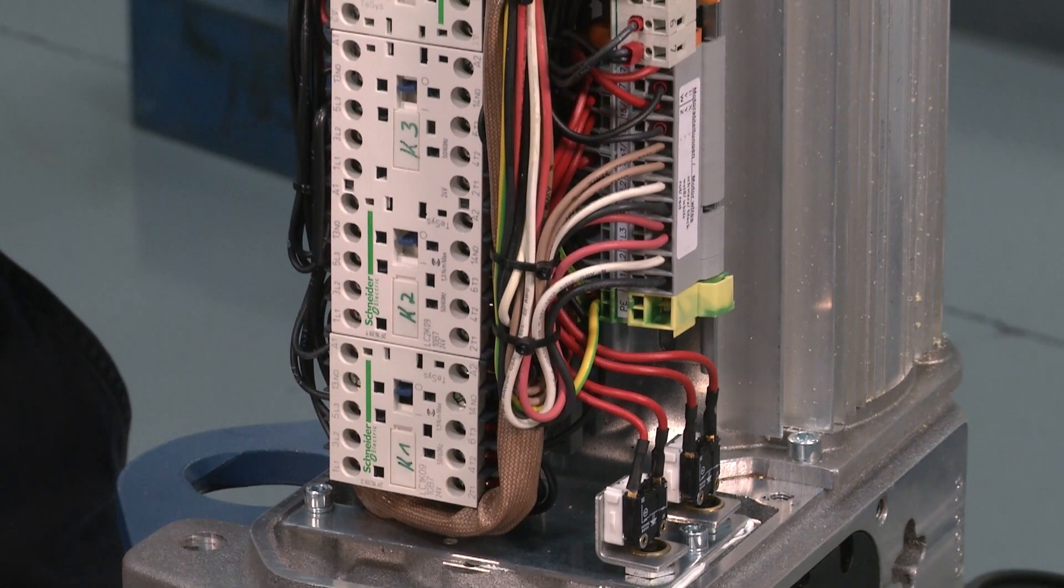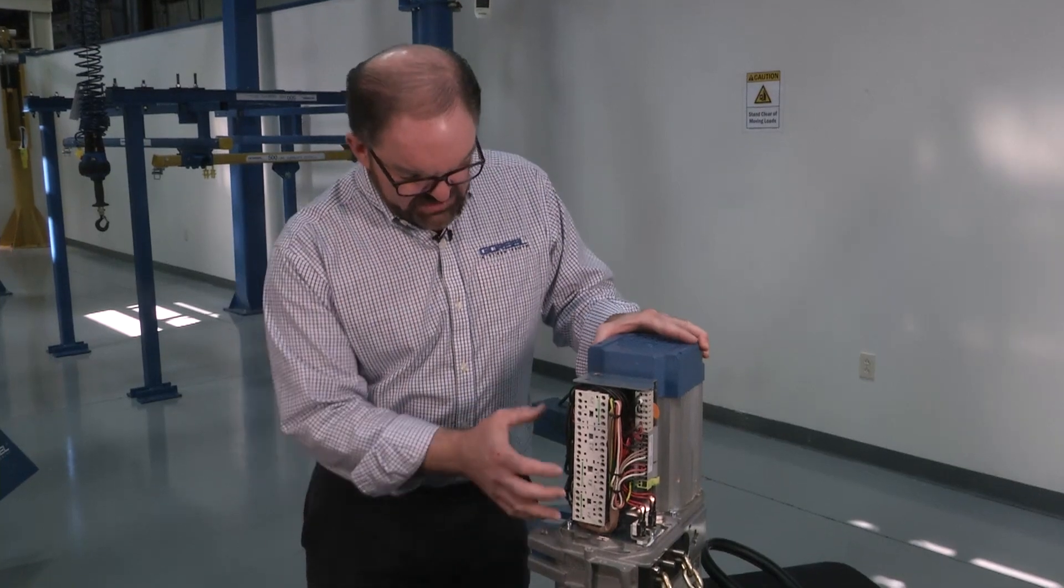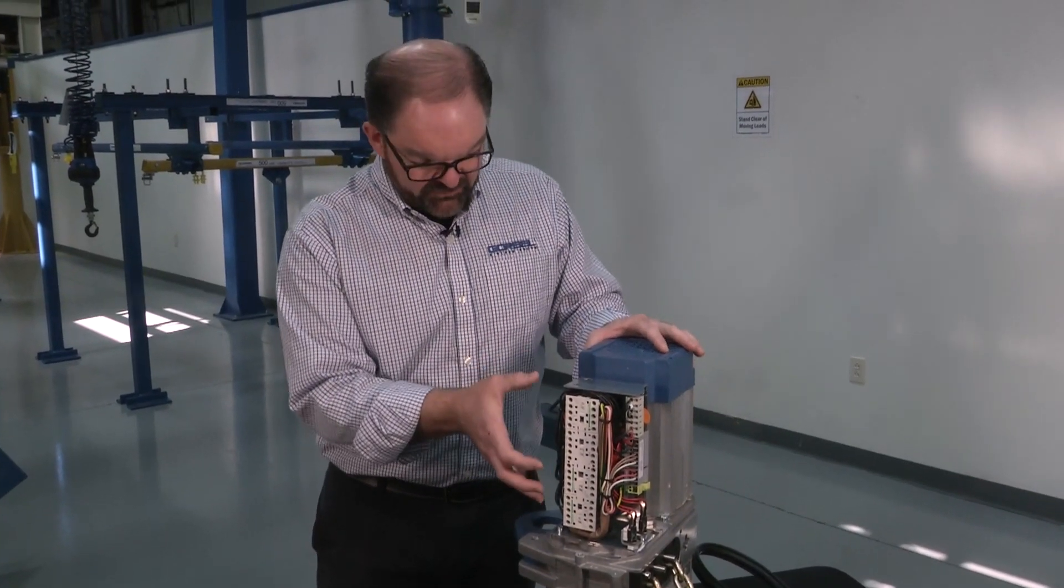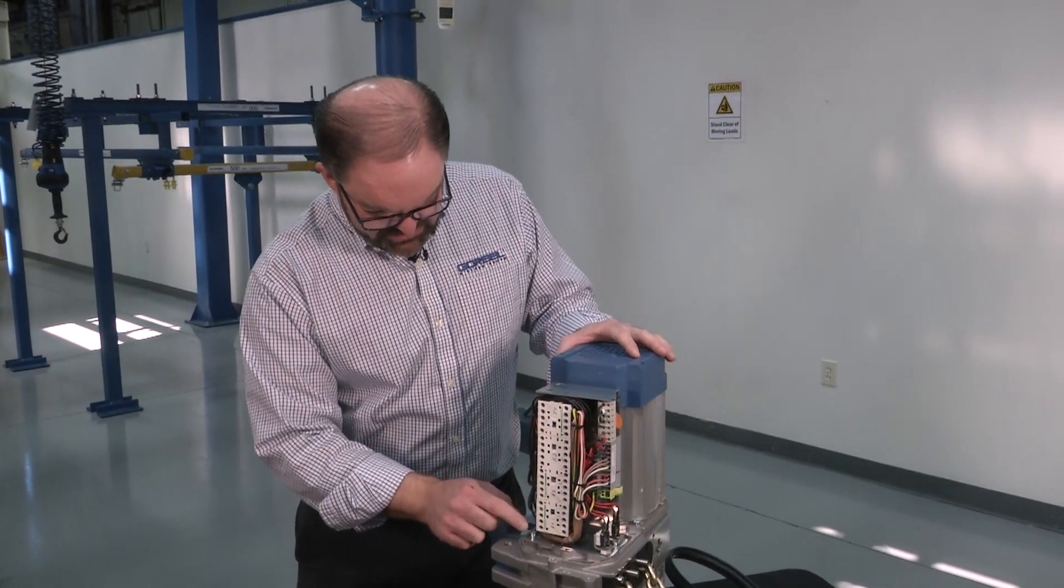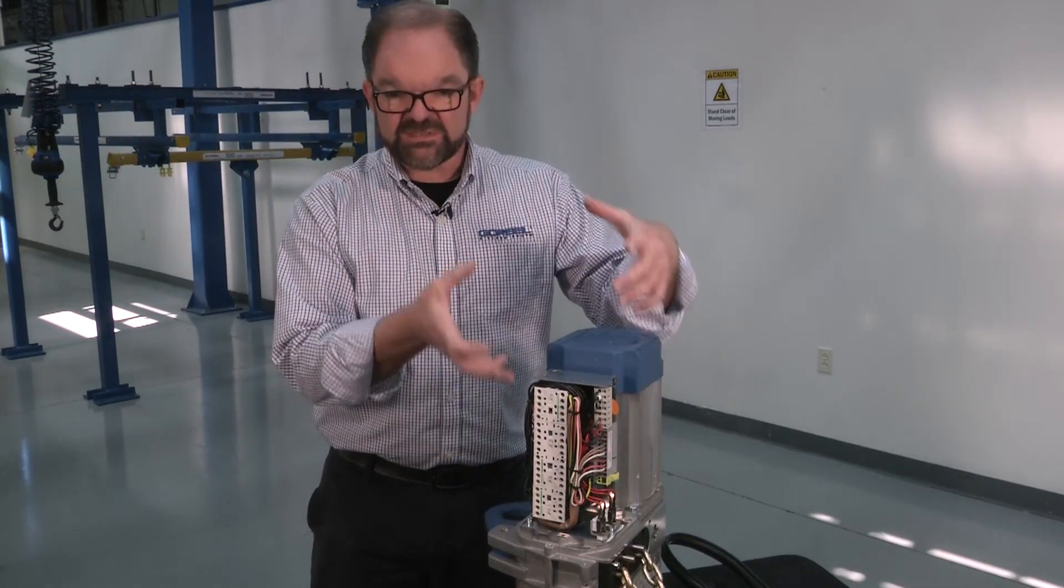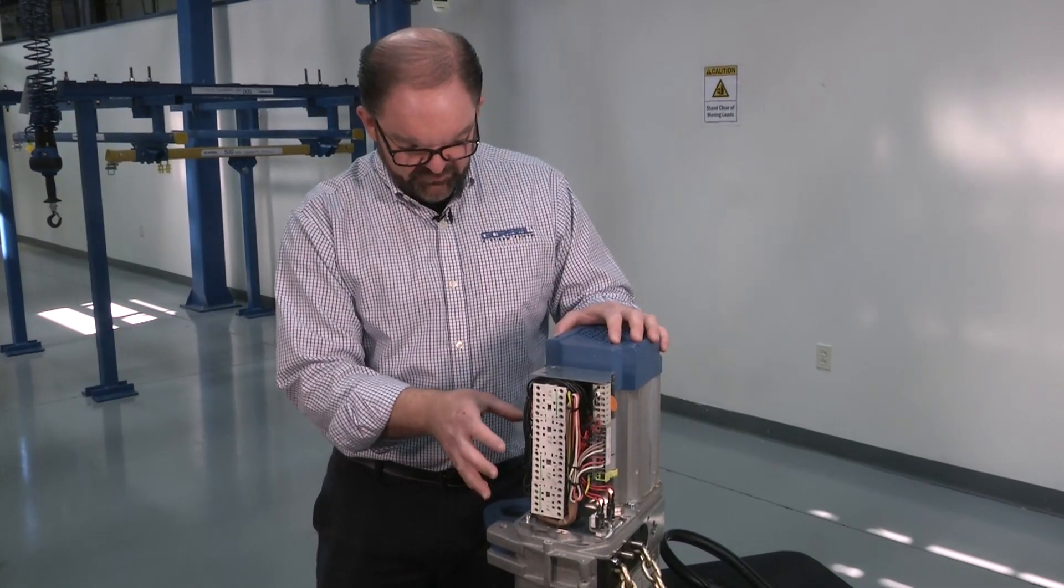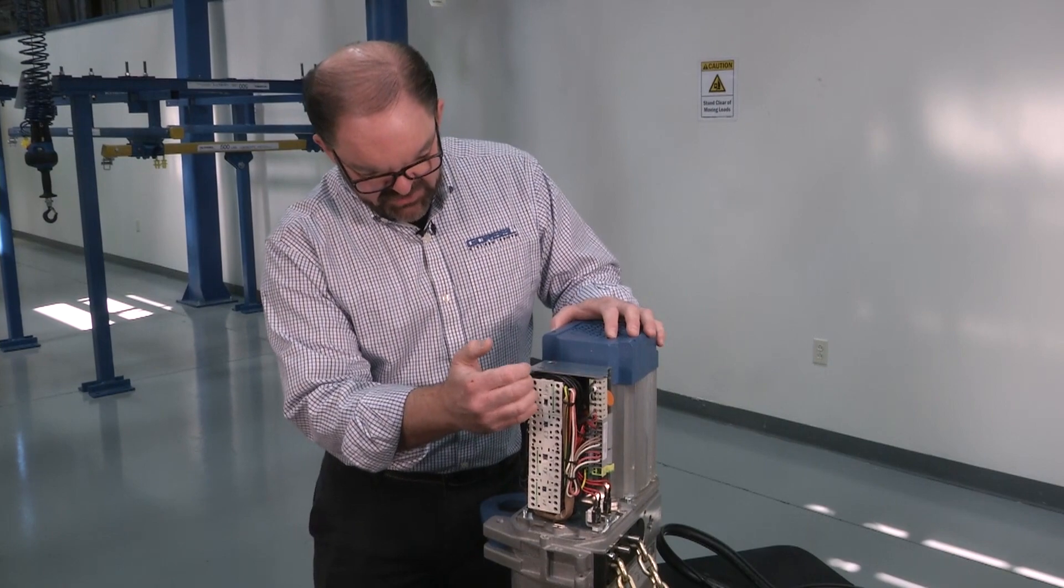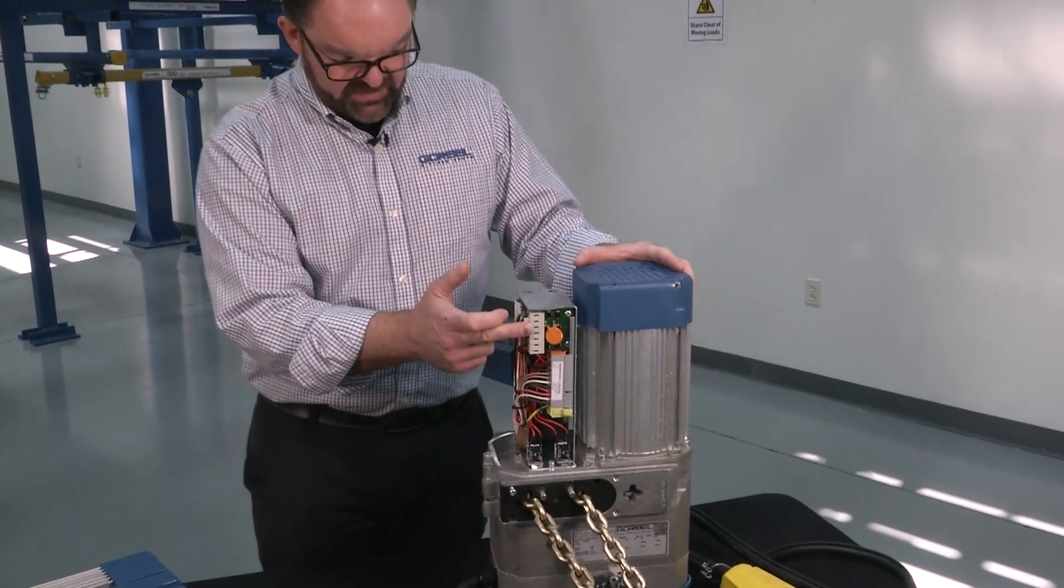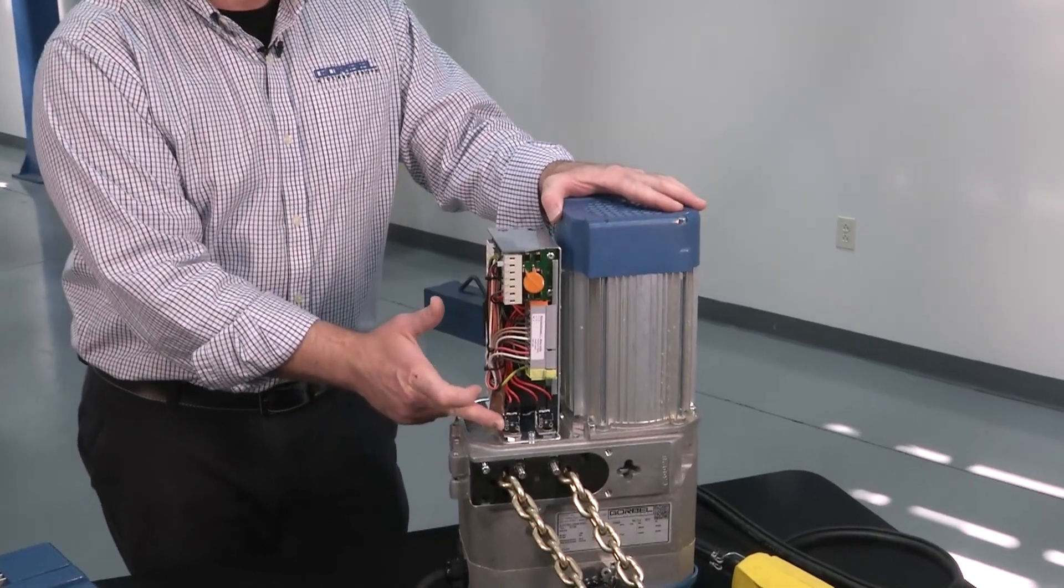So one thing you'll notice here is these contactors can be replaced individually if they ever need to be replaced. But also you'll see there's two pieces of hardware on either side of this module. You could actually replace this entire module in one fell swoop, and then you would replace all your contactors, your brake rectifier, and your limit switches all at one shot.